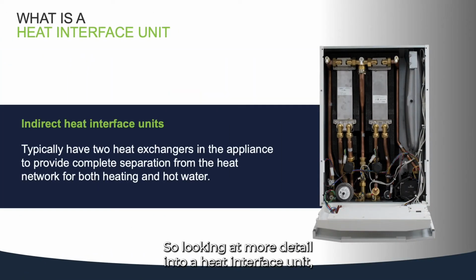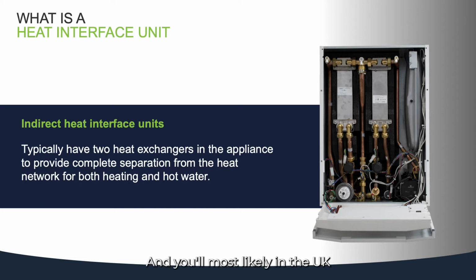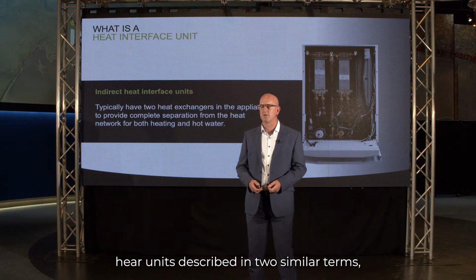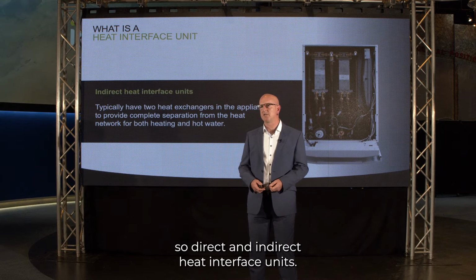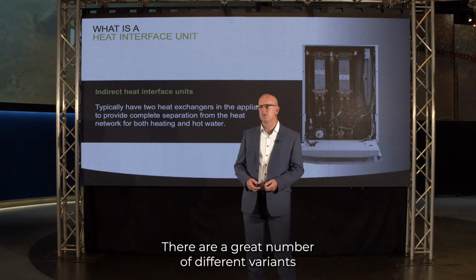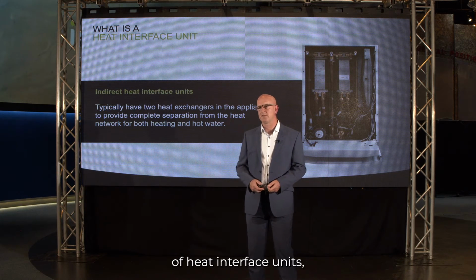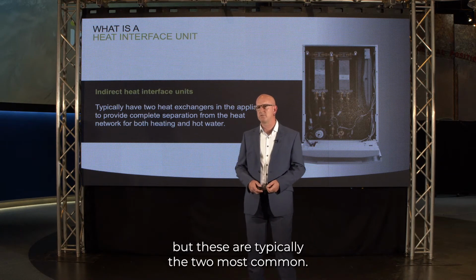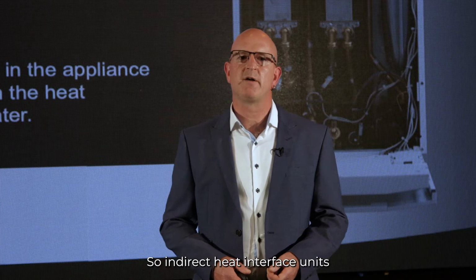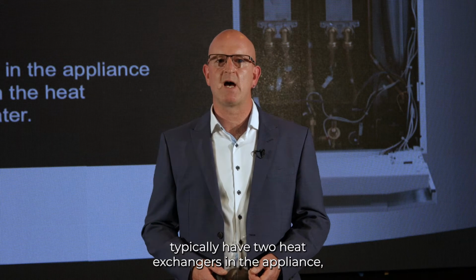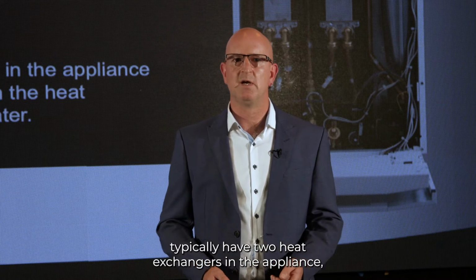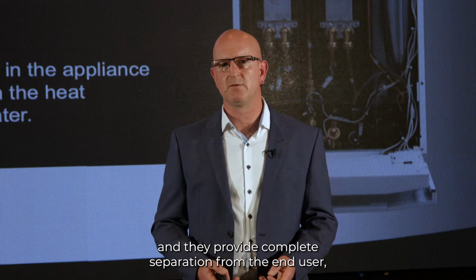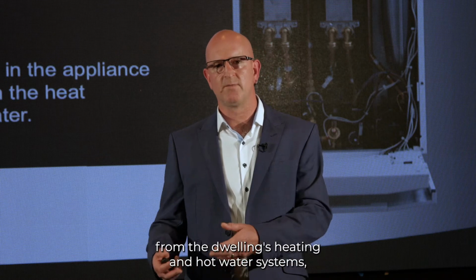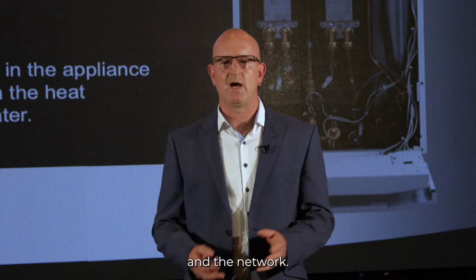So, looking at more detail into a heat interface unit, what actually is it? And you will most likely in the UK hear units described in two similar terms, so direct and indirect heat interface units. There are a great number of different variants of heat interface units, but these are typically the two most common. So indirect heat interface units typically have two heat exchangers in the appliance, and they provide complete separation from the end user, from the dwelling's heating and hot water systems and the network.